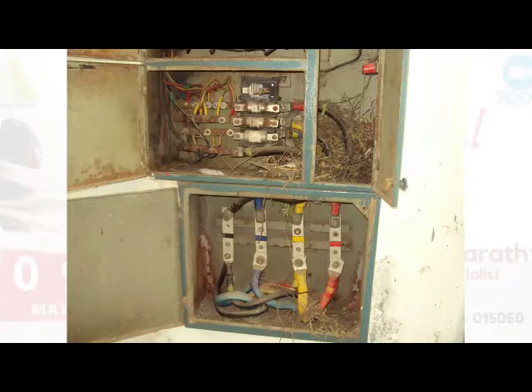Then ensure the right PPE is in good condition. Even the latest government guidelines for post-lockdown industry operation say this clearly. Always ensure the right PPE in good condition, because gloves left somewhere may get damaged internally due to rain or open conditions. Check that PPEs are in good condition and are the right rating - meaning the right voltage and current rating, which is 100% mandatory for electrical operations.